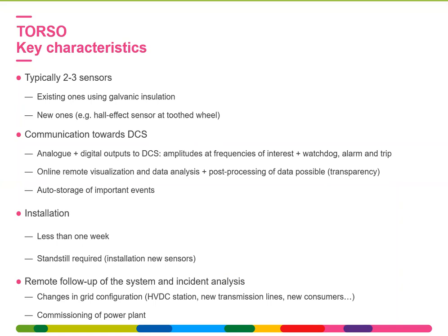You have the potential of having online remote visualization. So in real time, you see how the torsional vibration amplitudes are behaving, and more detailed post-processing of the data is also possible, again for transparency reasons. Any important event is automatically stored on the PC. And typically you have a circular buffer because you generate a large amount of data. Every timestamp of every pulse has to be stored. So typically you have a circular buffer of a couple of weeks, for instance, and any important event is then stored permanently on the hard drive.